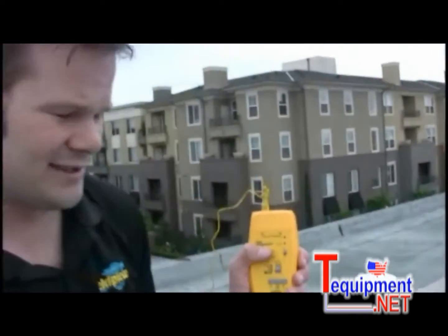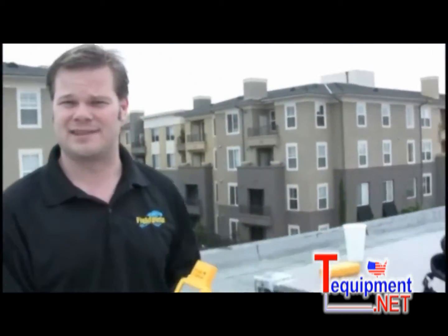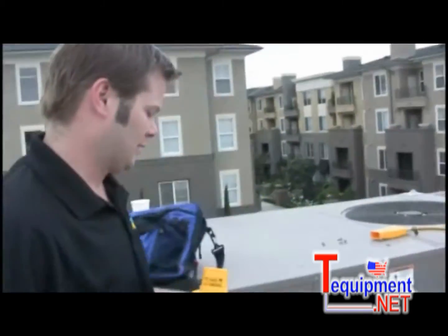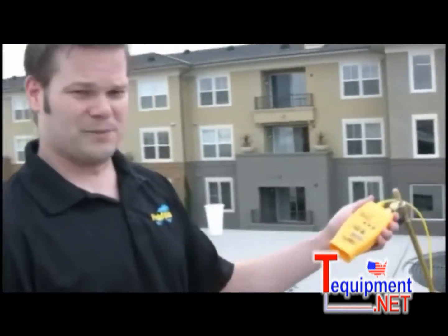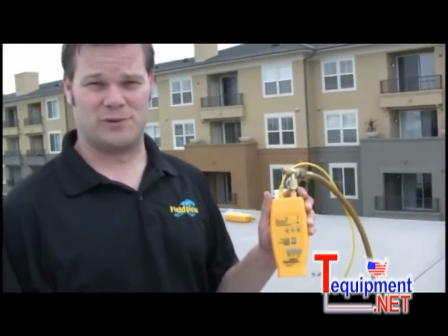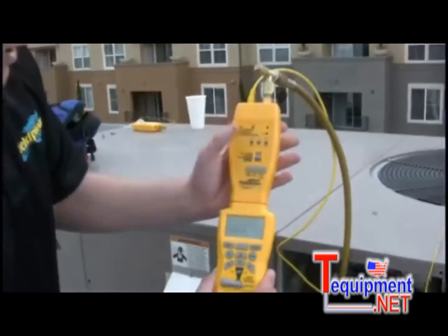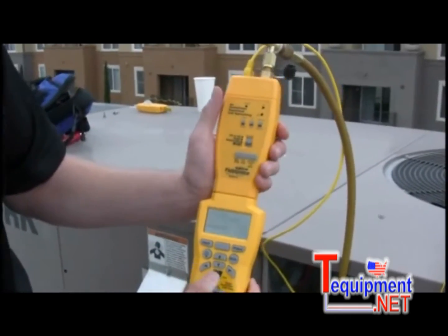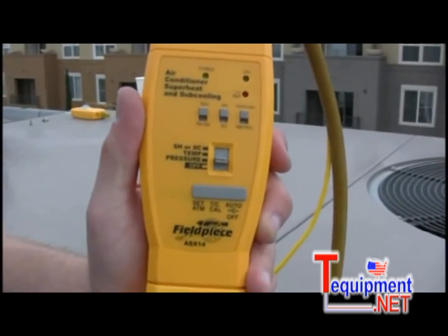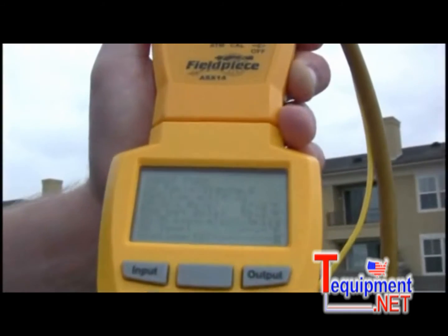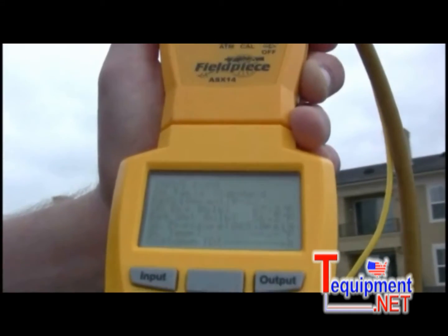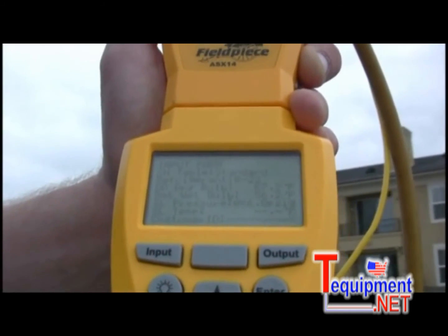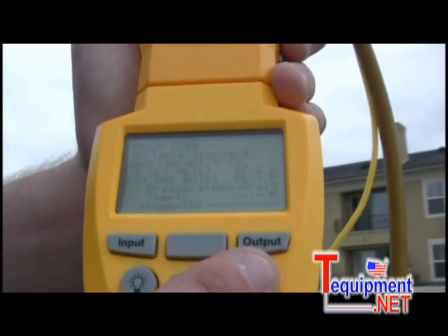Now I'm going to go back to the condenser side of the system and get my suction line pressure and suction line temperature. So I get those two measurements with the ASX14. This is our superheat and subcooling head. So I'm just going to attach that on, go up to pressure, press enter on the HVAC Guide to start taking my pressure, and you see that I have a 65 psi as my pressure. So what I'm going to do is press enter to lock that in, then suction line temperature.